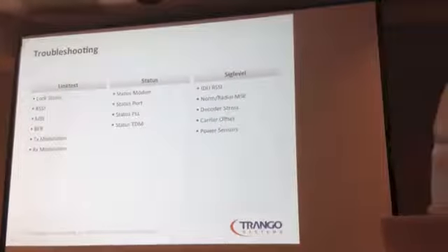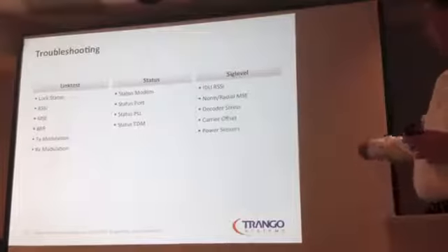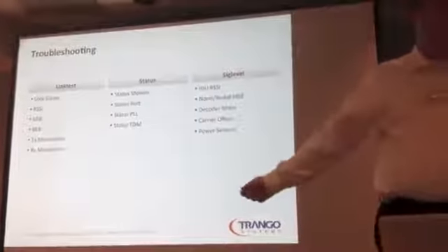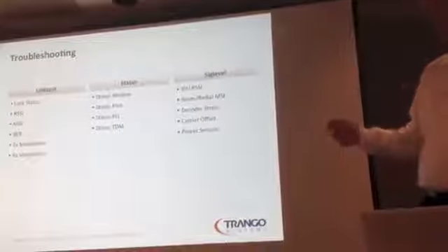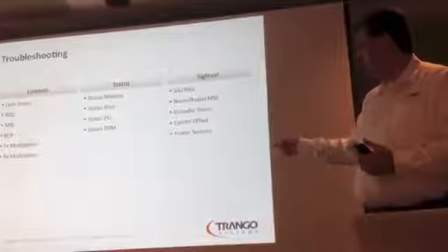SIG level will be the next point we would turn to if you think you're having an issue. Okay, and we're going to talk about what all these mean in a second. But it's going to give you some very critical information that's only used for diagnosing a problem. Okay, it's a lot of detailed signal information. First up is the IDU RSSI. This is going to show you what the RSSI is coming into the IDU or the OMU.